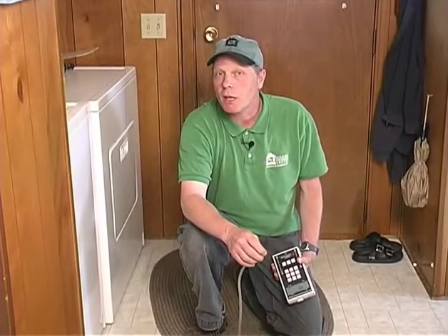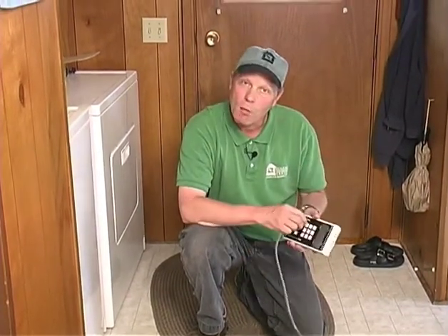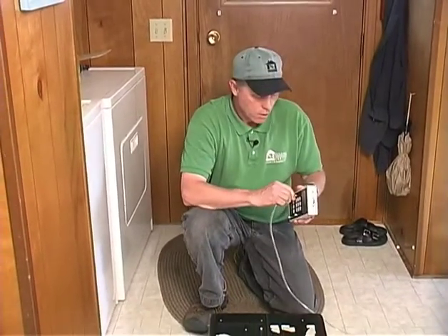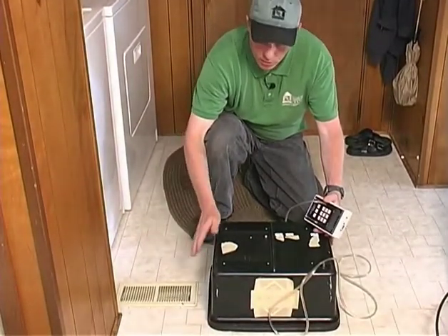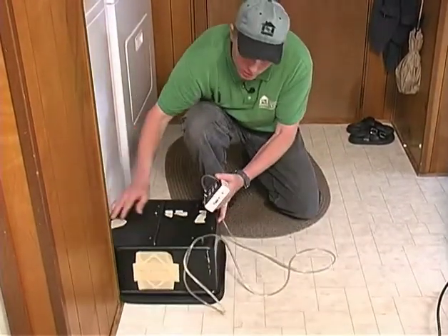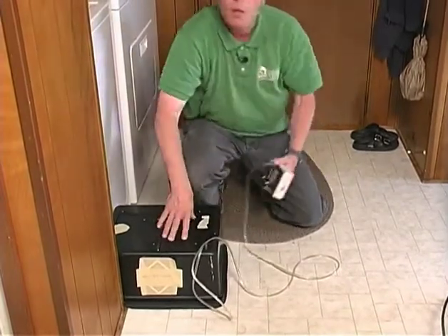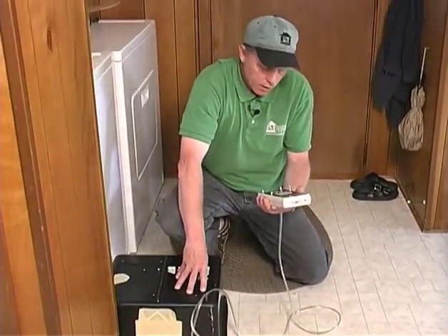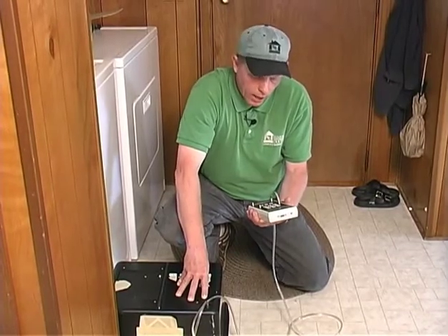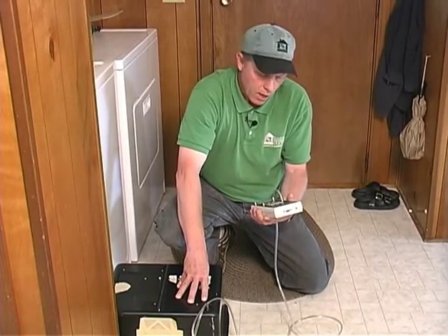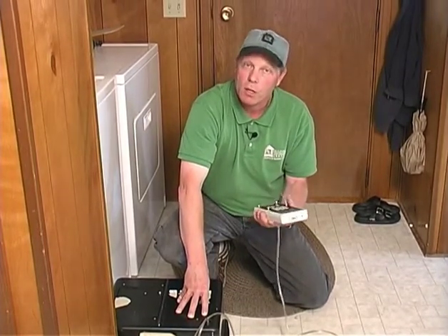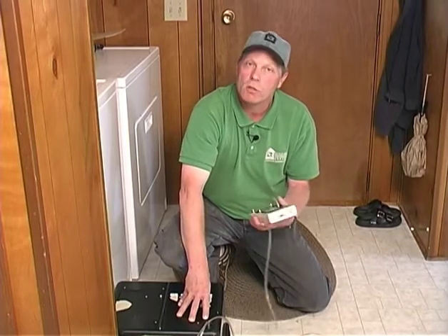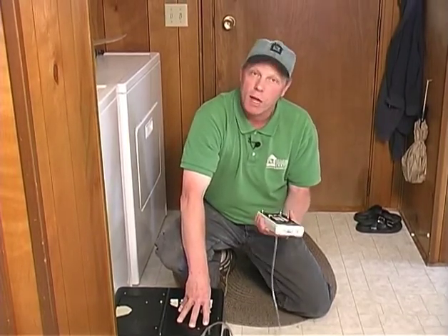My blower door is running, and I'm getting set up to do my pressure pan test. I'm going to hook up my manometer so I can read a pressure through the hose and over this duct register. So I'm going to place the pressure pan over the duct register, put a slight pressure on it, seal it reasonably tight, and it looks like we have a number of less than 1 here. That is a typical standard in the industry. At 1 or below, we consider this area of the duct tight.